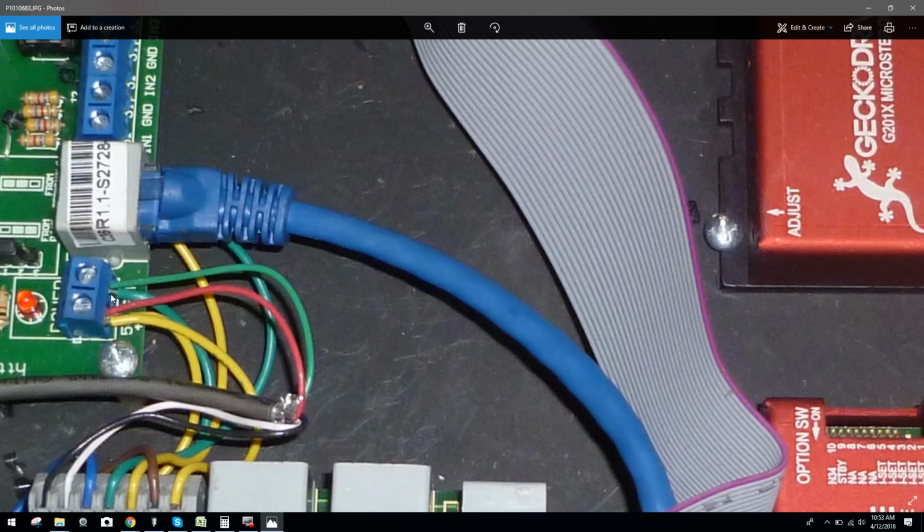This potential client dropped over $5,000 on this system. That is a ridiculous amount of money to have to rebuild an entire controller just because of lack of detail and honestly an ignorance to the actual context of what he's building. And we can see that right here. If this individual went on Gecko's website and actually did the research on wiring the drives, one of the first things they talk about is daisy chaining. This is totally inept for wiring this system.